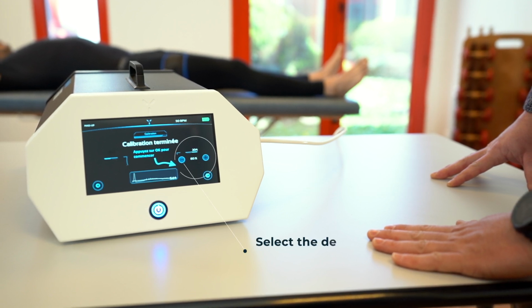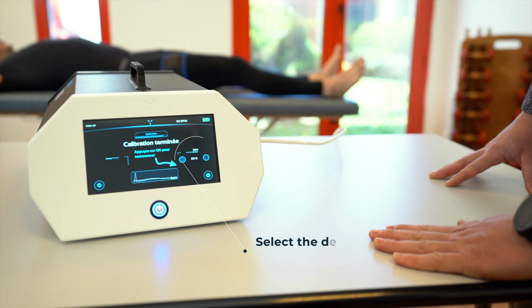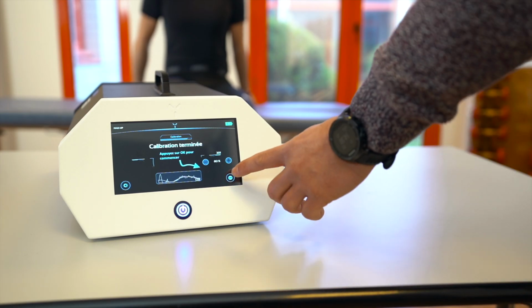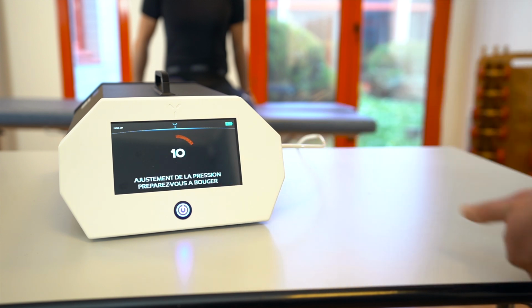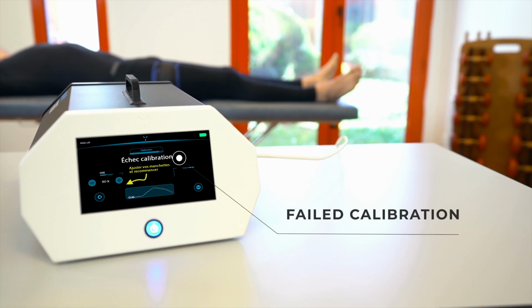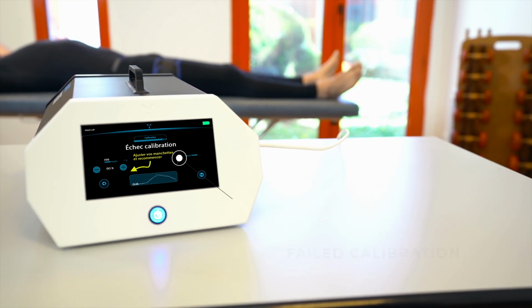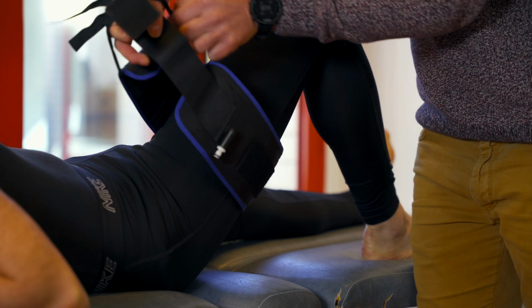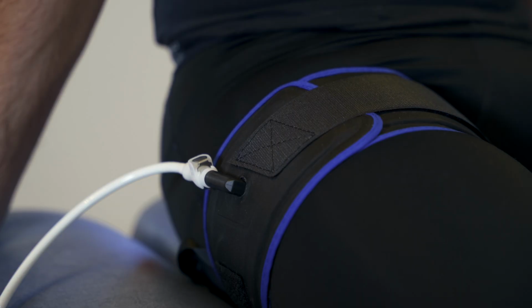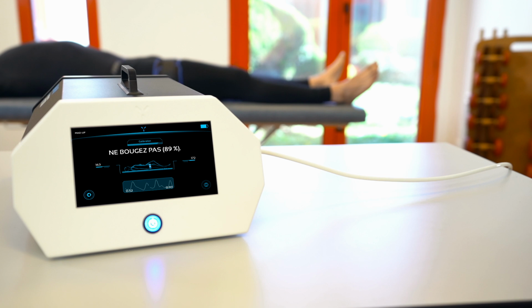Once calibration is successful, select the desired pressure level and place yourself in an exercise position. When you press OK, the device will take 10 seconds to recalibrate and set the occlusion percentage for that position. If the device indicates that calibration has failed, check the positioning of the cuffs and tubes. After these checks, run the calibration again.